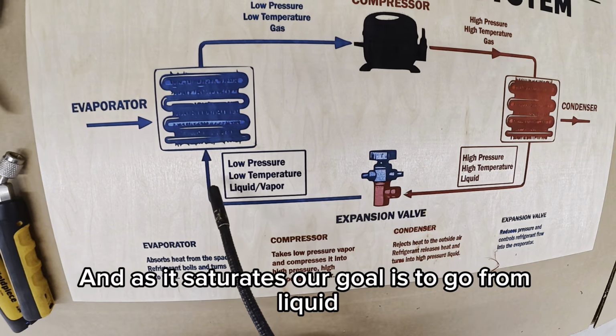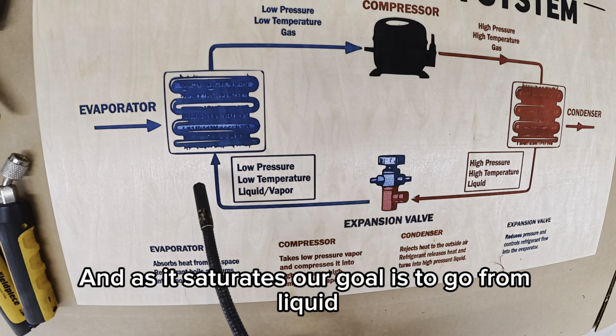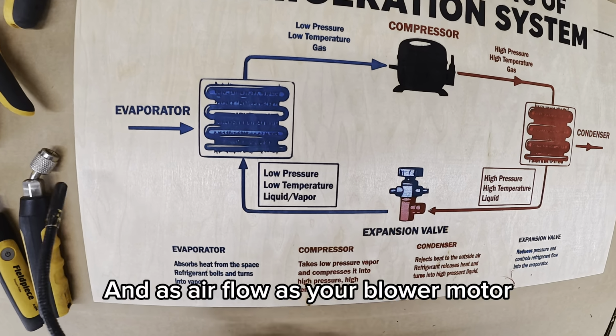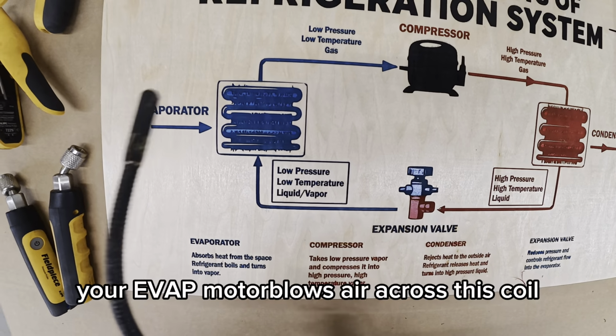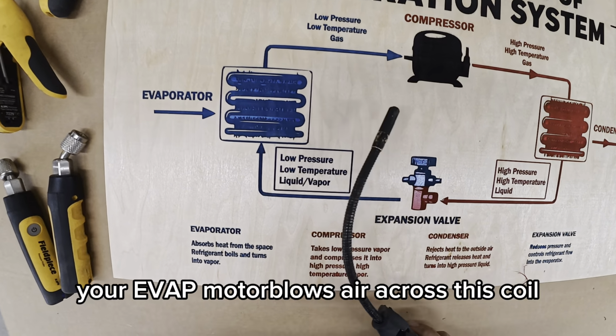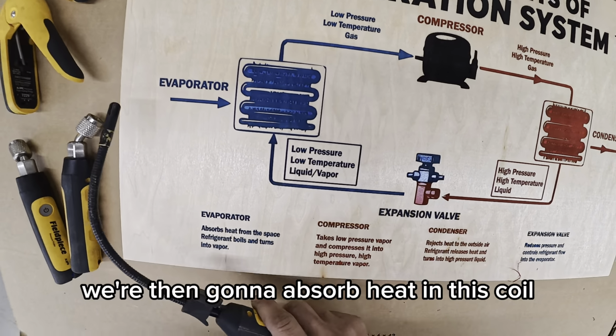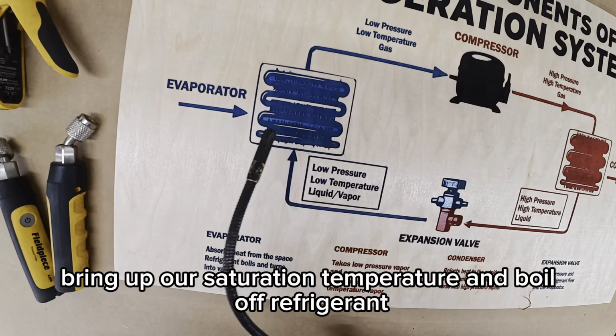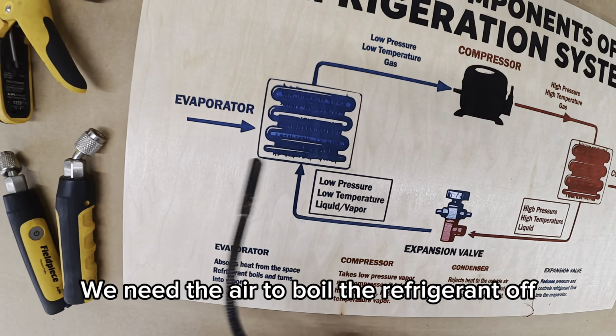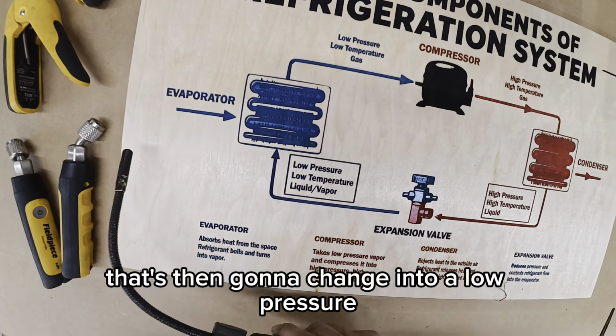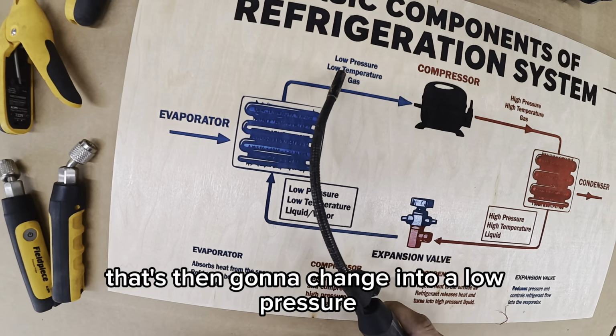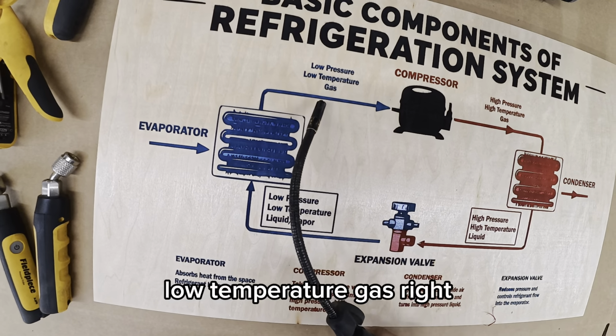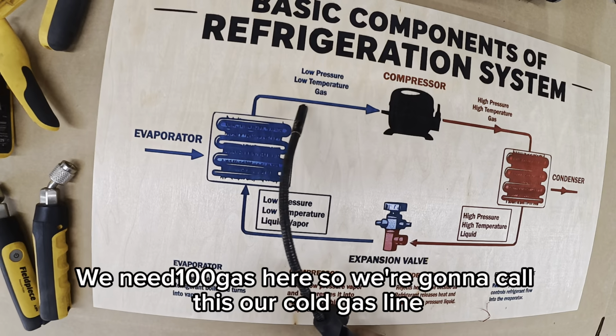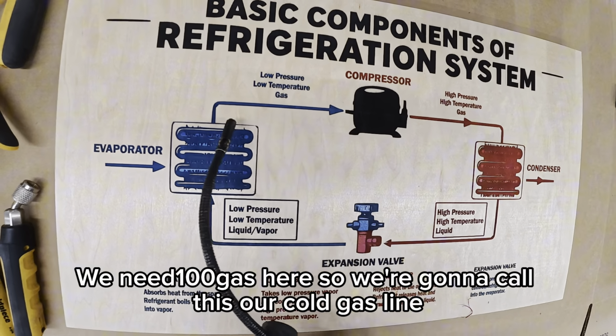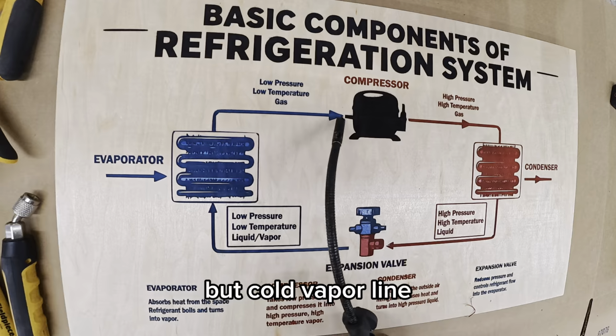And as it saturates, our goal is to go from liquid, right? And as airflow, as your blower motor, your evap motor, blows air across this coil, we're then going to absorb heat in this coil, and that warm air is going to help bring up our saturation temperature and boil off refrigerant. We need the air to boil the refrigerant off. That's then going to change into a low pressure, low temperature gas, right? We need 100% gas here, so we're going to call this our cold gas line, cold vapor line.